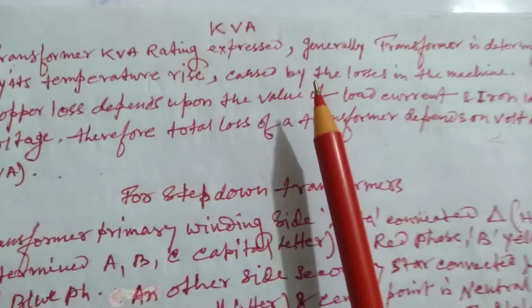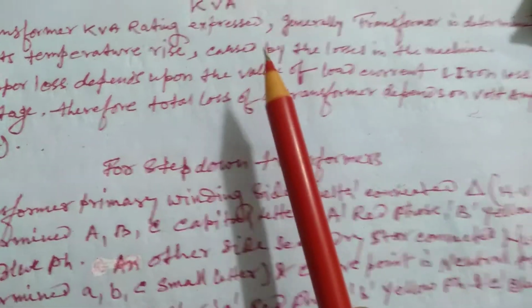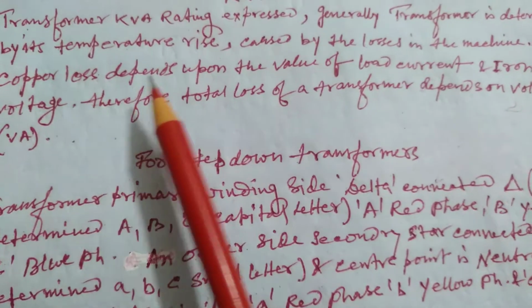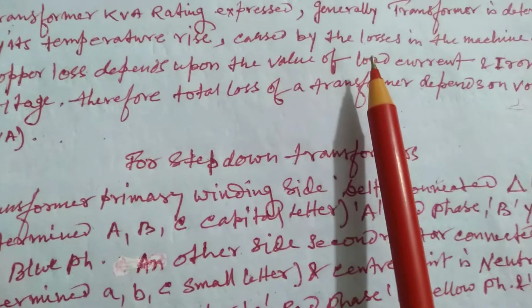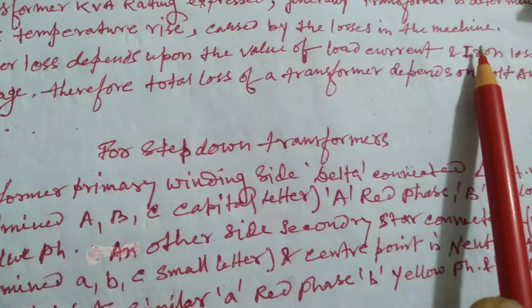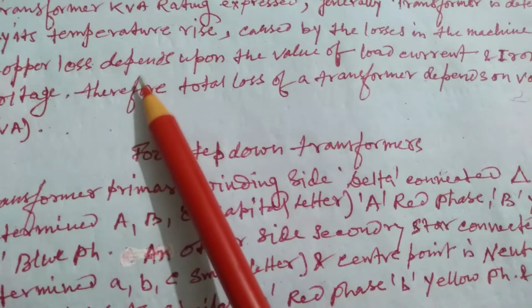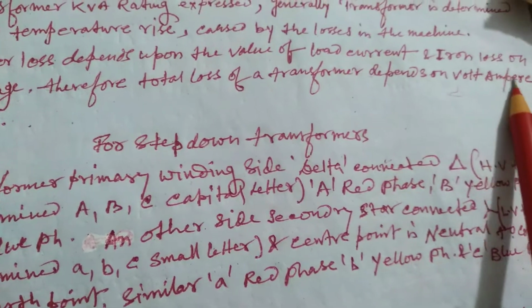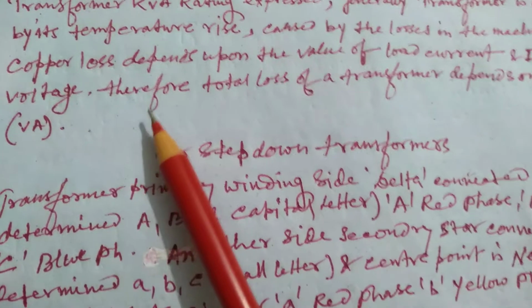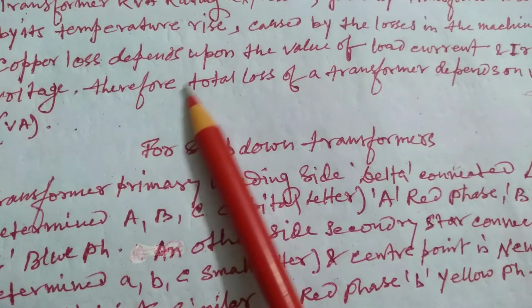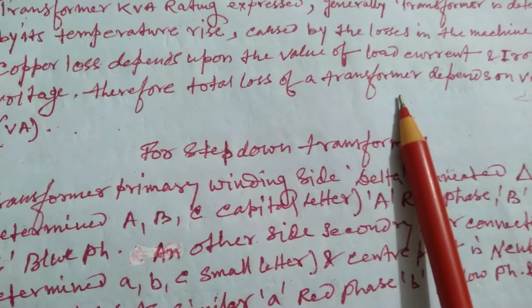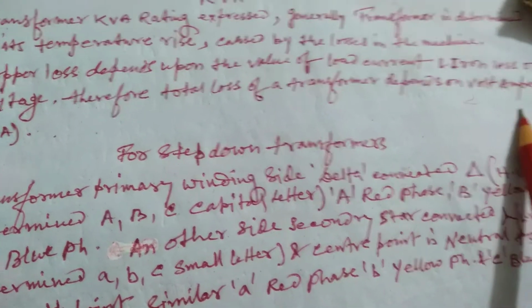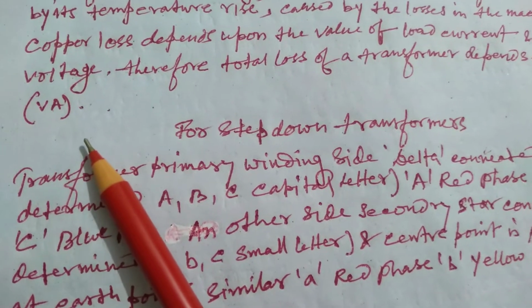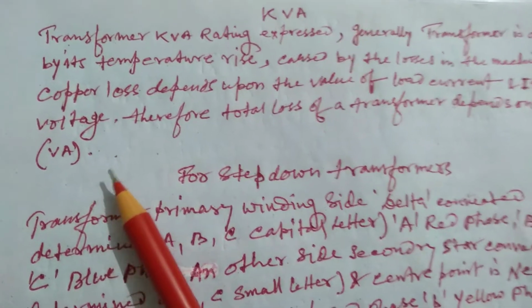KVA in transformer, the KVA rating is expressed generally. The transformer is determined by its temperature rise caused by the losses in the machine. Copper loss depends upon the value of load current, and iron loss on voltage. Therefore, total loss of the transformer depends on volt amperes, VA. This is the rating in KVA.